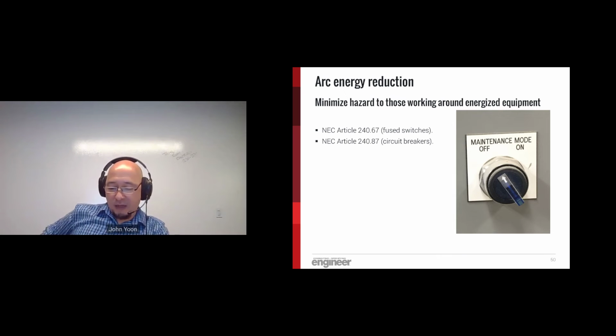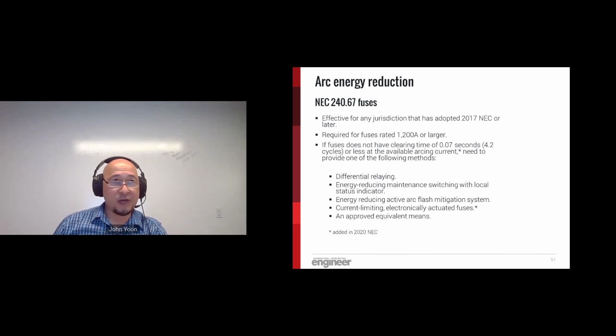The NEC started to address arc energy reduction starting with the 2011 version. The original requirement was just limited to circuit breakers in 240.87. However, the requirement for fuse switches, that you see here, 240.67, wasn't added until the 2017 version and recently just took full effect. How we accomplish this arc energy reduction for fuses and circuit breakers is slightly different, and we'll talk about this in the next few slides.